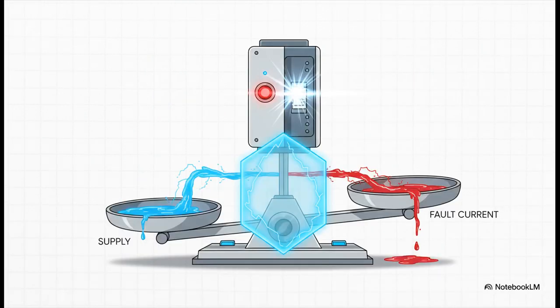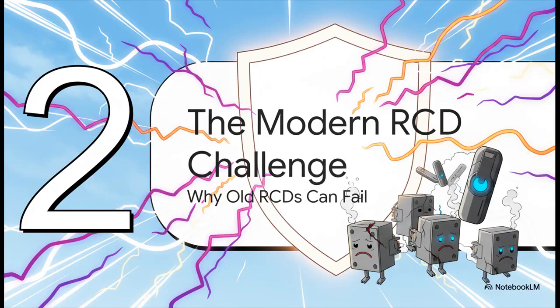And this is the RCD's heroic moment. It is constantly watching that balance. The second it senses even a tiny difference, that residual current, we're talking as low as 30 milliamps, it trips. It just slams the power off in milliseconds, way faster than a human could ever react, and long before lethal shock can do any real harm. Now that principle is just beautiful, and it has saved so many lives.